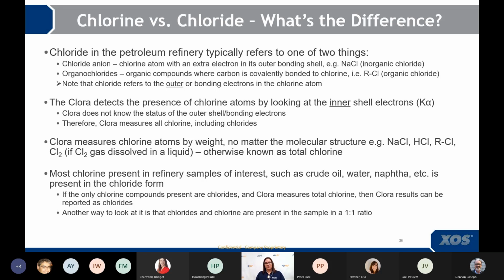Note that for both of these chlorides, it refers to what's going on in the outer or bonding electrons in the chlorine atom. The reason that we use the terminology chlorine is because the Clora detects the presence of chlorine atoms by looking at the inner shell electrons, the K alpha to be specific. The Clora does not know the status of the outer shell or the bonding electrons. Therefore, your Clora actually measures all chlorine, including chlorides. Clora measures chlorine atoms by weight, no matter the molecular structure.